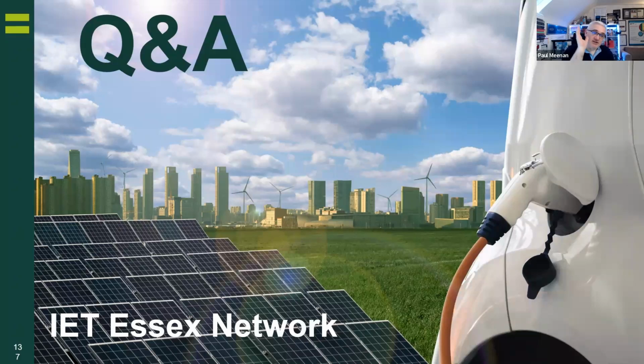Section 8 is very clear that there's a requirement to ensure, if you're a prosumer, the minute you switch out of the national grid, your fault current levels must still allow disconnection, and your polarity and earth loop impedances must all still ensure a safe installation. More importantly, you're going to have to switch your earthing arrangement out, so you may end up with characteristics of supply switching rapidly.